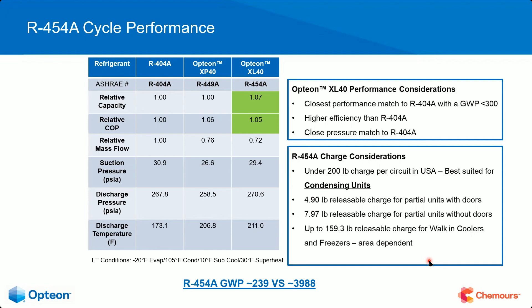Now, up to 159.3 pounds of releasable charge for walk-in coolers and freezers. That's going to depend on your area dependent. What that means is cubic feet. All right. And I'll show you that here in a little bit. But first, I want to compare 454C. Again, it meets all the regulatory requirements, as we talked about earlier, similar equipment design requirements, POE oil, lower and medium temp refrigeration, in some cases, AC and heat pumps.